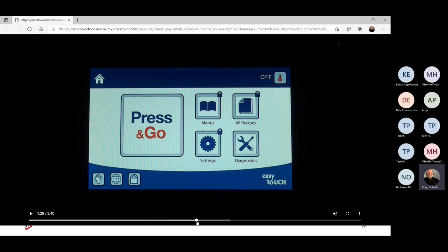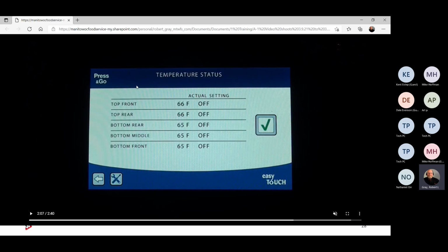Go ahead and play this for a second. So in the off screen, or anytime that you see this thermometer up here, you can simply click on it, push it, touch it, whatever you want to call it. And it should take you to your temperature status screen. In the off screen, you're not going to have any set temperatures because it's off, so it's not looking at it. But it will give you your current temperature readings from your thermocouples. Again, your thermocouples are grounded K-type. They measure millivolts and send them to the SIB, and the SIB then converts it over to Fahrenheit or Celsius, depending on where you're at.